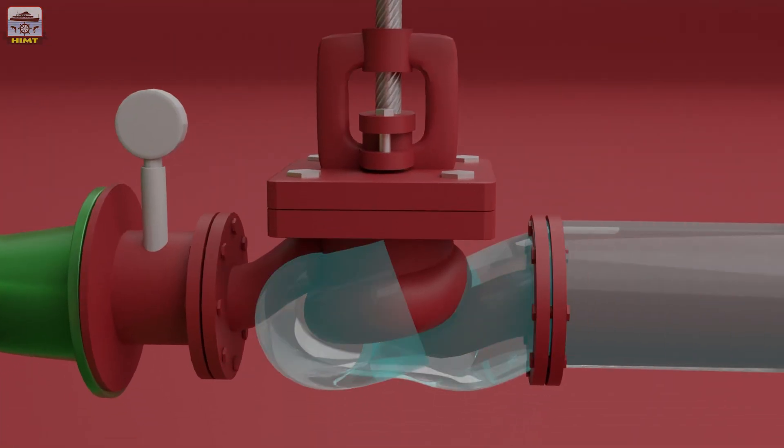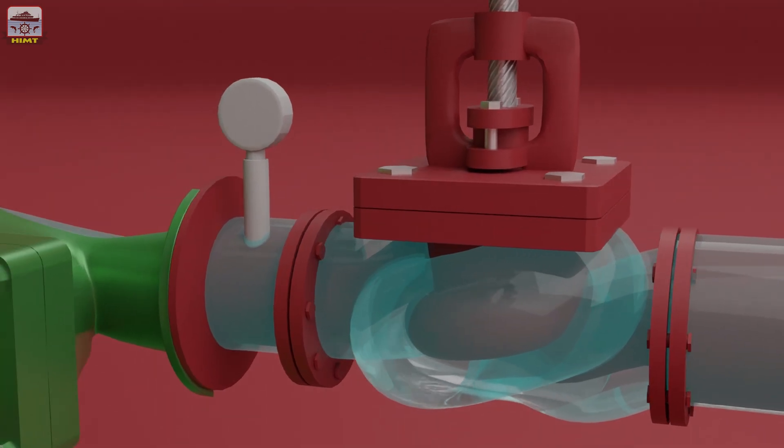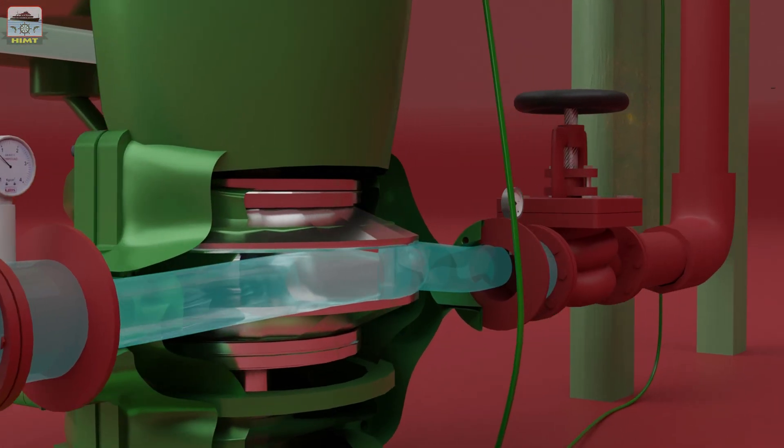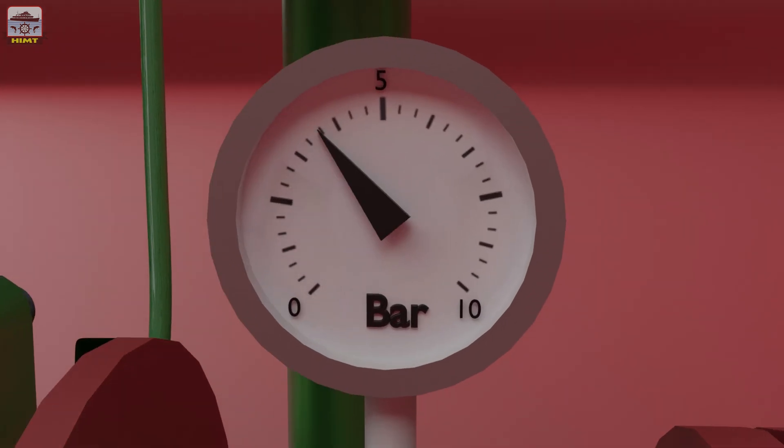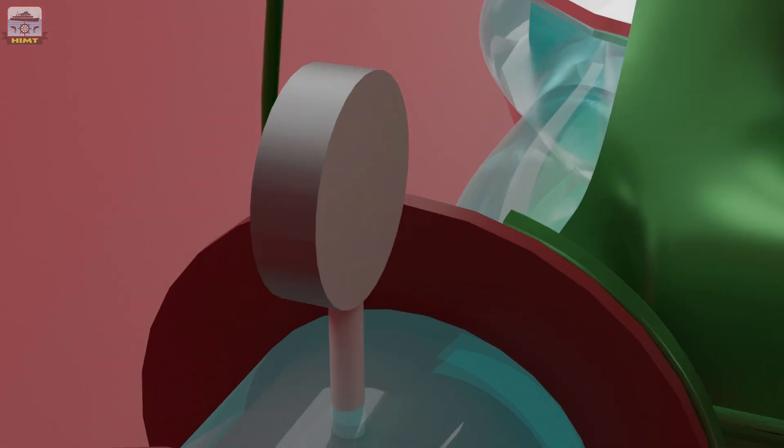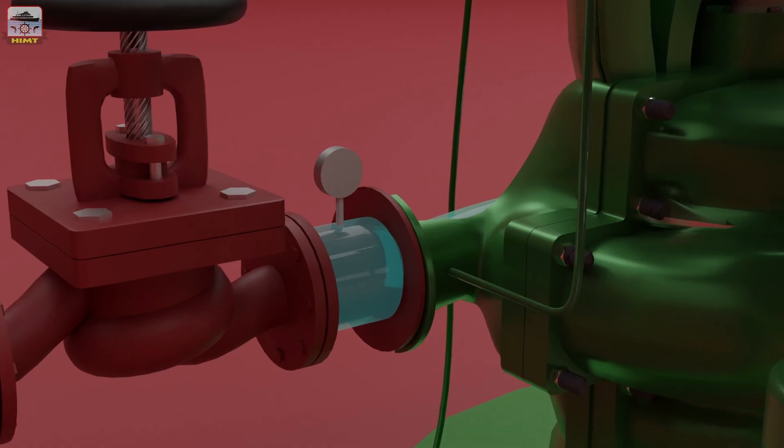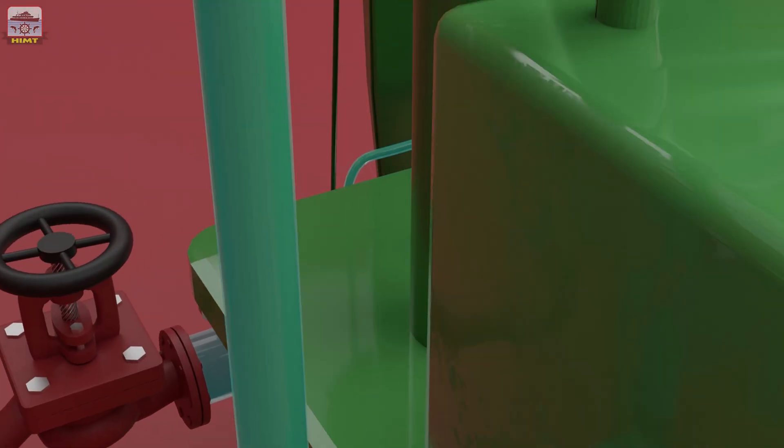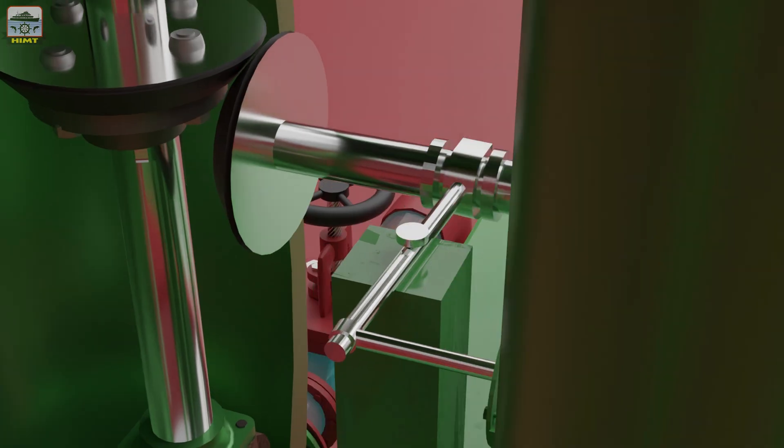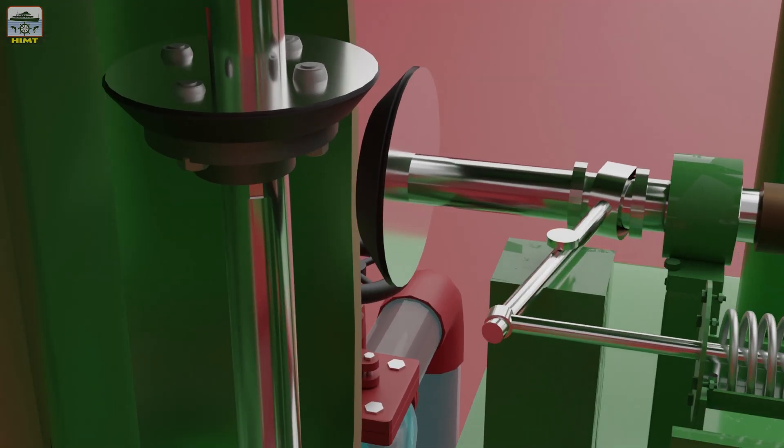Water rises up in the suction pipe and fills up the main pump casing. Once the casing is filled with water, the pump develops pressure, and this pressure acts on the auto cylinder which disengages the primer pump from the main pump.